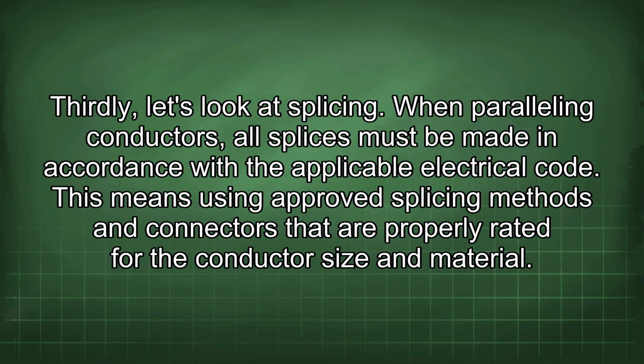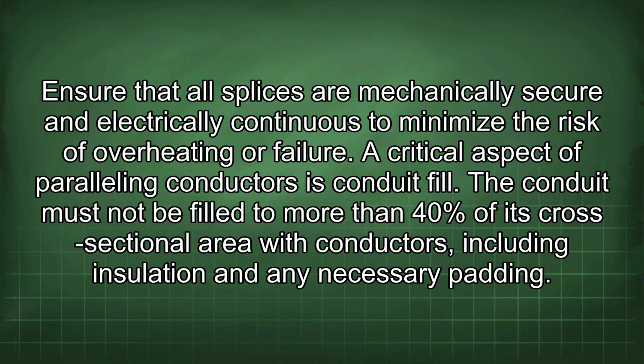Thirdly, let's look at splicing. When paralleling conductors, all splices must be made in accordance with the applicable electrical code. This means using approved splicing methods and connectors that are properly rated for the conductor size and material. Ensure that all splices are mechanically secure and electrically continuous to minimize the risk of overheating or failure.